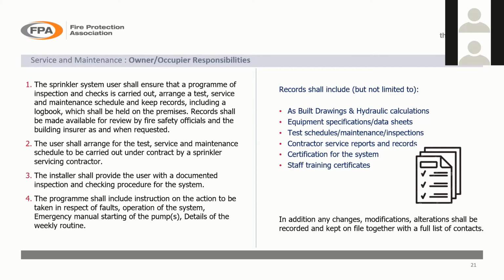If not, you might just have to employ a sprinkler contractor to come in and do a site survey, produce drawings, and retrospectively do a calculation on the system, and get a maintenance company to come in and look at the condition of your pumps and tanks and things like that. But records should be maintained, but in the event that they're not, then you've got to go back retrospectively and try and find that. And we do find quite a few projects that we look at where there are no records on site, even jobs that were completed in 2010, 2011. Sometimes, 10 years later, the records are one of the things that seem to disappear quite quickly, which is a bit of a surprise.